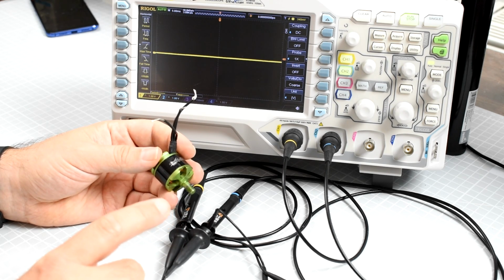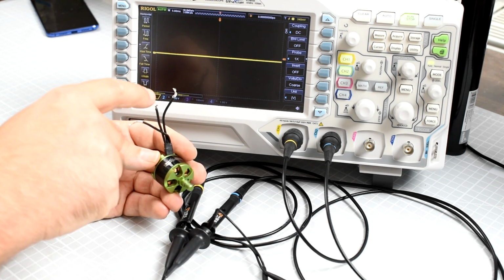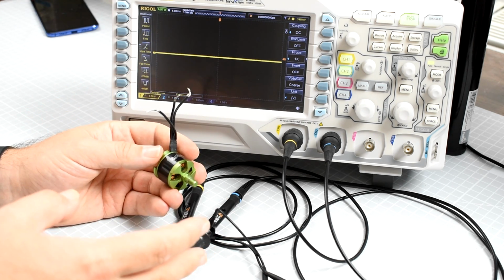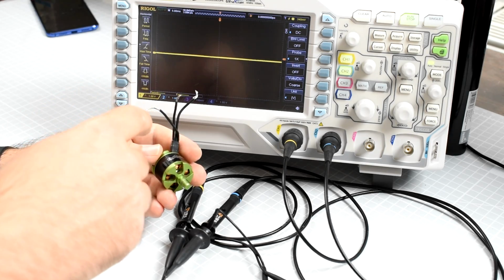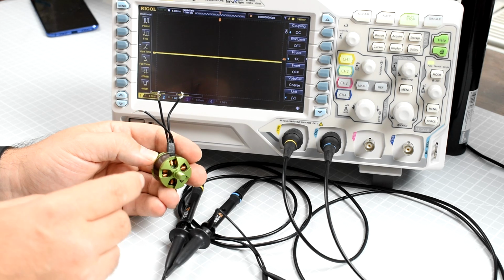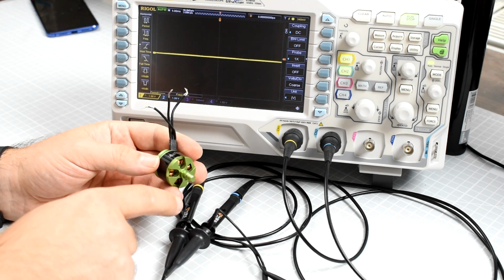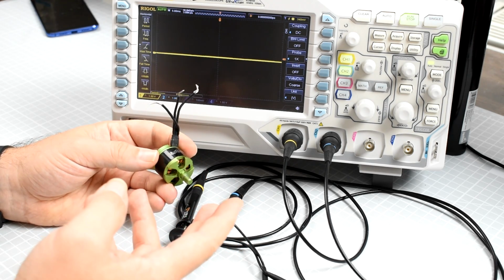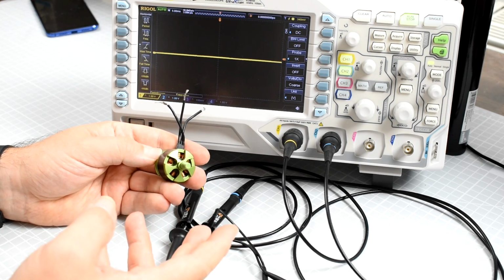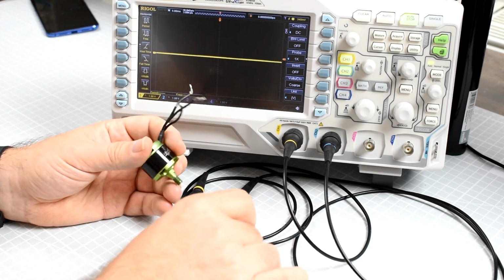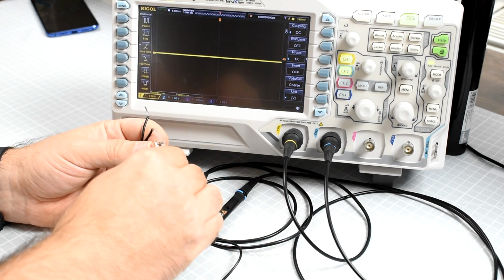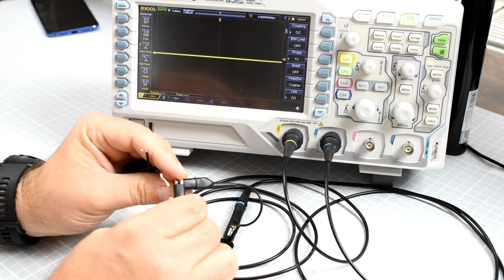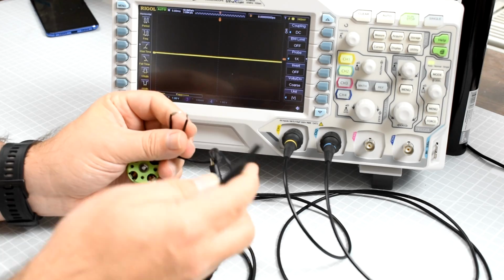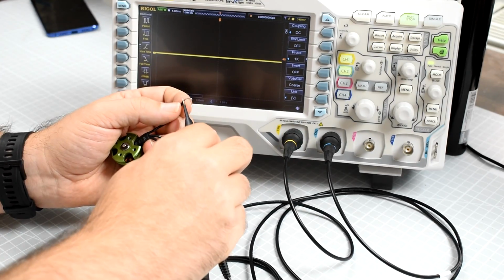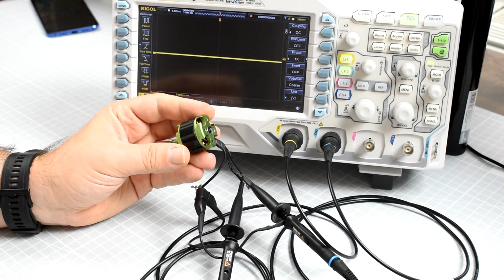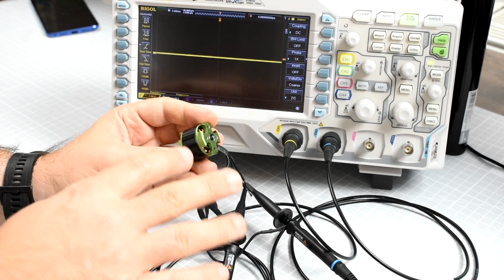Now this is important. I can connect and check only two phases. I cannot connect all three phases because the grounds on my scope are not isolated, and when I try to connect the third phase, the grounds will make a short circuit and everything will go bonkers. With this termination of the motor, there is just no common ground. I would have to have some super fancy devices that isolate grounds between phases, but I do not have them. So what we're going to do right now is connect two grounds of the probes, of the channels on the scope, to one of the phases, and then connect the remaining phases to the remaining connectors. So we will be able to see what's happening on two phases, assuming that the third phase of the motor is the common ground between them.